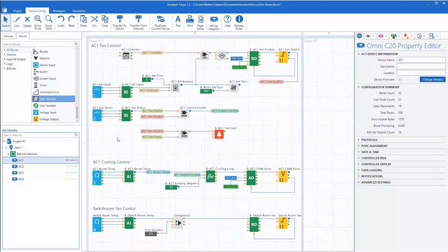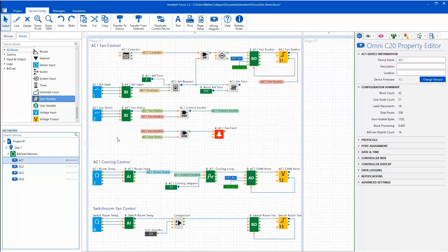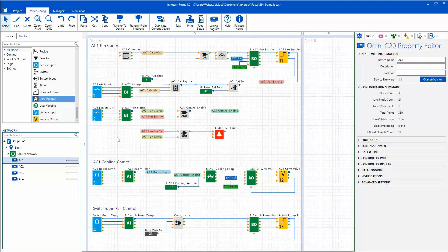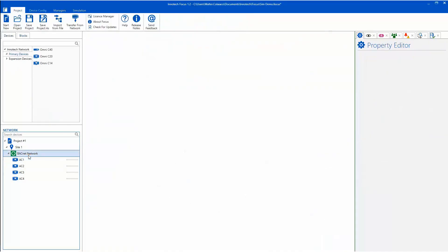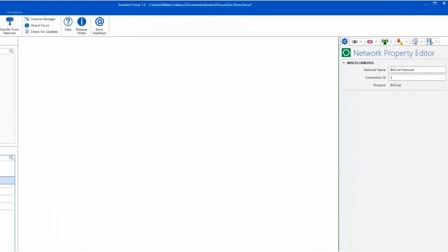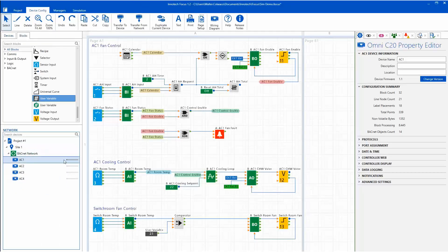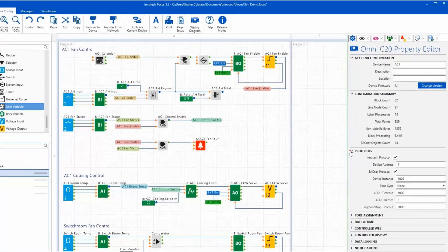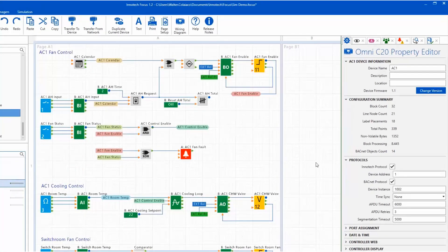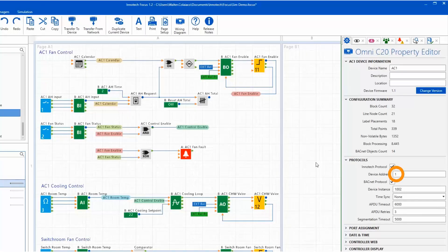The simulation session can be connected to the ICOM Communications Server if required via Focus Simulator Connection. The first item to check is the Network ID within Focus. Simply click on the network, in this case the BACnet network, and locate the connection ID assigned. In my case the ID is 3. Also check the Innotech device address of the Omni controller. This is required for the ICOM connection properties.